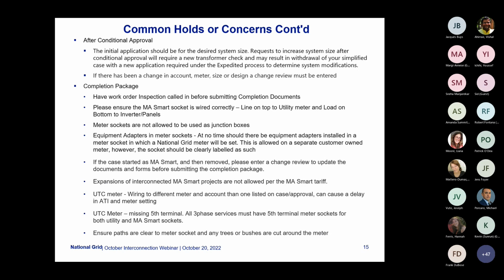We also get a lot of these issues for missing a fifth terminal — any three-phase service requires a fifth terminal meter socket. So if you go to a premise with three-phase service and the utility socket isn't a fifth terminal, and you're adding solar, you must update that utility meter socket to a fifth terminal, and your Mass Smart socket should also be a fifth terminal socket. Also ensure, as mentioned earlier, that there's a clear path to your meter sockets, with no trees, bushes, or anything blocking them.